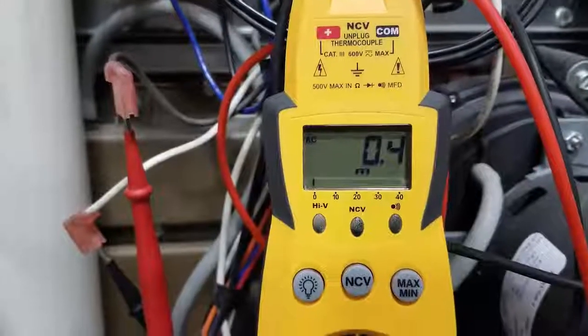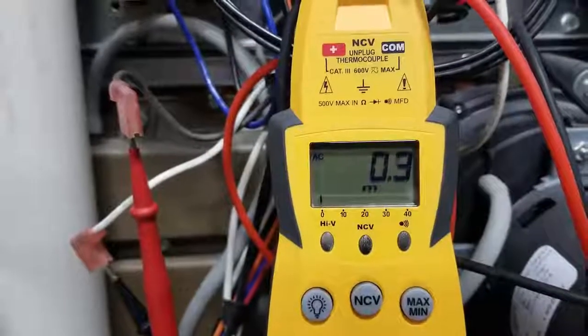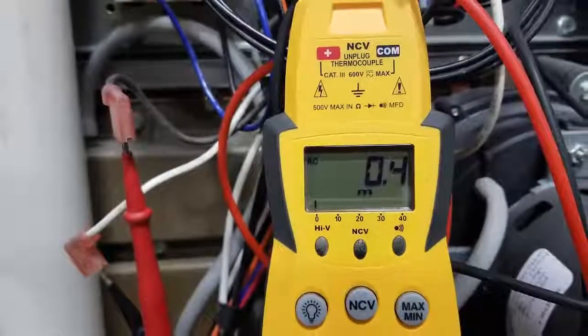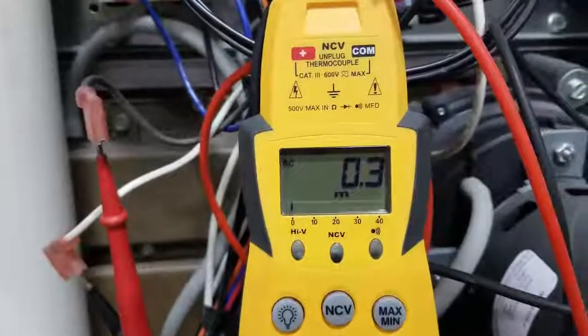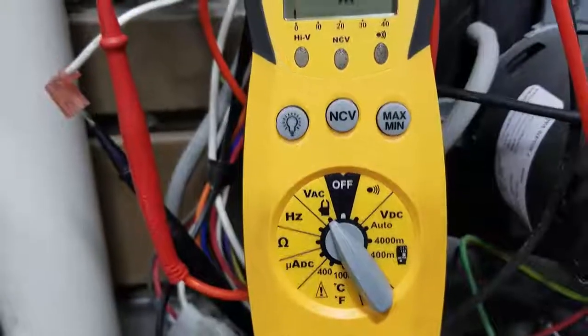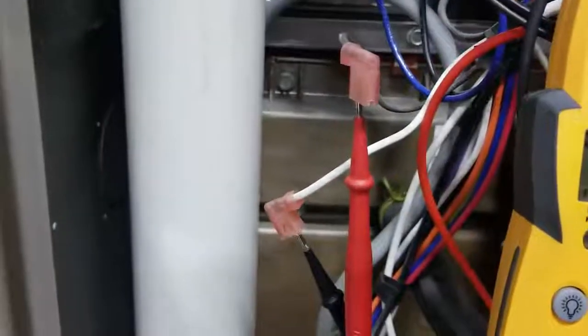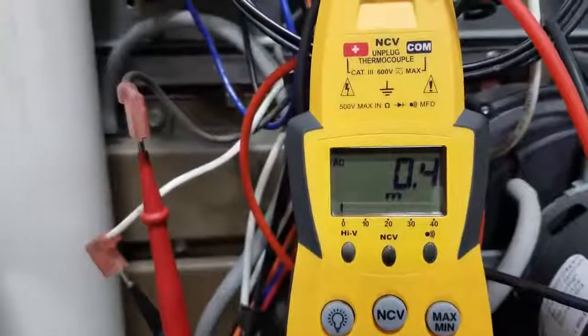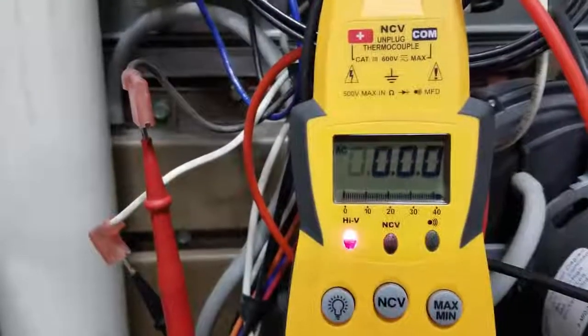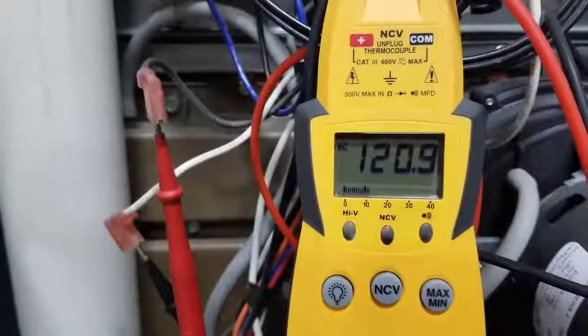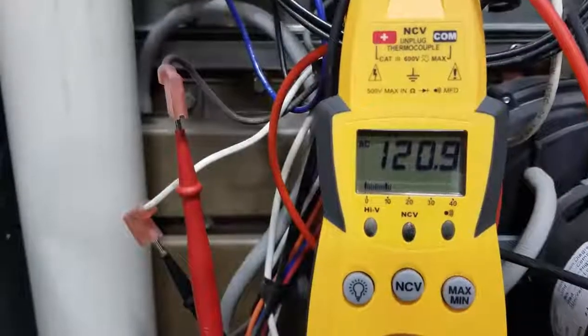Okay, now we're going to watch a quick video demonstrating the process for checking power to the primary side of the transformer and power from the secondary side of the transformer. Okay, I've got my leads pulled off of the high voltage side of the transformer. I've got my meter set for volts AC. We've plugged our meter leads into those 2 wires going to the transformer. And when we flip the power to the furnace on, we should see 120 volts. That means that we have power to the transformer.